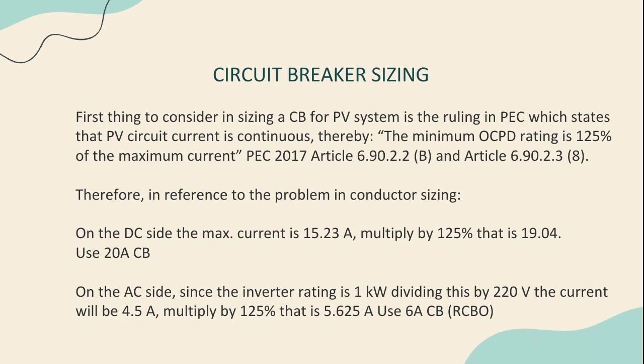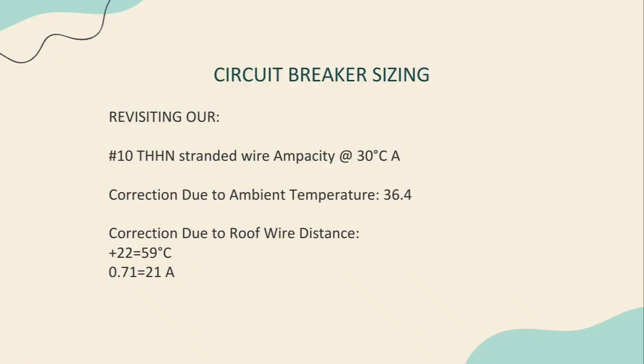And sa AC naman is, since the inverter rating is 1 kilowatt divided by 220 volts, the current will be 4.5 ampere multiplied by 125%, so that is 5.625 ampere. So gagamit tayo dito ng 6 ampere circuit breaker para sa AC or RCBO. Circuit breaker sizing. Revisiting our number 10 THHN or thermoplastic high heat nylon stranded wire ampacity at 30 degrees Celsius. Correction due to ambient temperature 36.4. Correction due to roof wire distance is plus 22 equals to 59 degrees Celsius. 0.71 equals to 21 ampere.